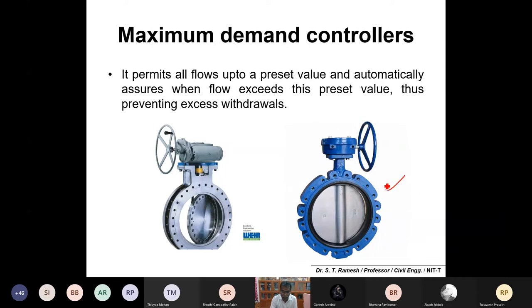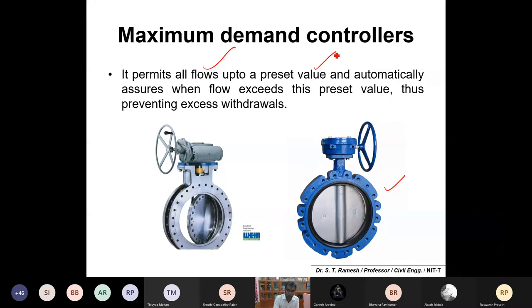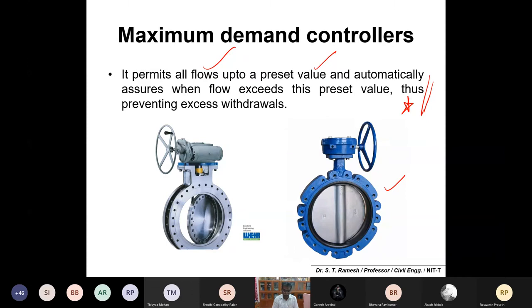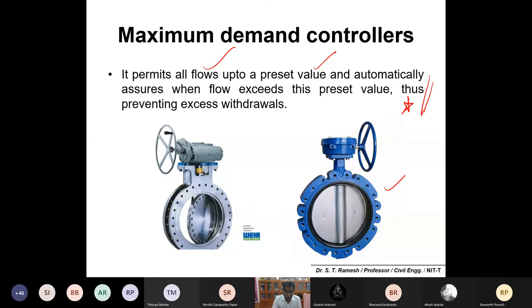Next are maximum demand controllers. These are connected to an automatic scanner system and will allow only the required flow. Please note: it permits all flows up to a preset value and automatically closes when the flow exceeds this preset value, thus preventing excess withdrawals. In city networks, manual operations are difficult, so automated systems are used. They fix a preset value to regulate flow, and once it is reached, it automatically shuts off and does not allow excess withdrawal of water.